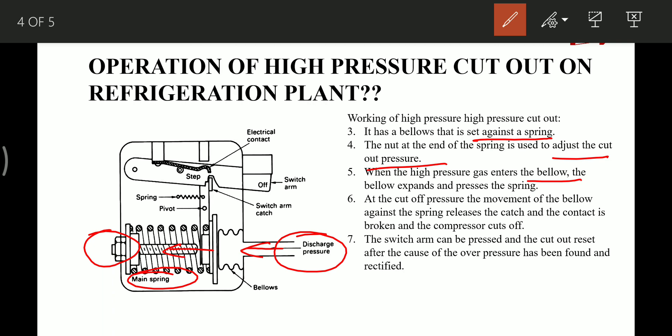At the cutoff pressure, when this cutoff pressure is reached, the movement of the bellow against the spring releases this catch arm and the contact is broken. This cuts off the compressor. The switch arm can be pressed and the cutout is reset after the cause of overpressure has been found and rectified.